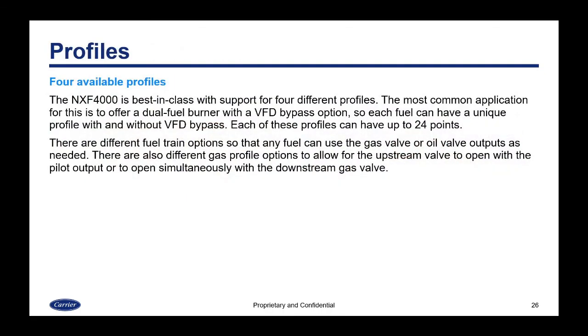So with the NXF4000, it has a best-in-class support for 4 different profiles. The most common application where you're going to use 4 profiles would be for a dual fuel burner that would have a VFD bypass option so that each of the 2 fuels can have a unique profile with a VFD bypass and without a VFD bypass for a total of 4 profiles. And each of those profiles in turn can then have up to 24 points.